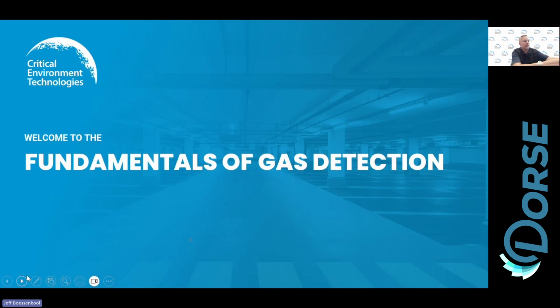We take a larger unit, which is similar to this guy here. We call it our CGAS SD, our sample draw. And we've got a nipple here and polytube going in and sampling that air within that room. The main controller would live outside of the Faraday cage, which is that MRI room, okay? So that we can continue monitoring those oxygen levels and making sure they're at a safe level. If they do get down below, I think it's 19.5 is a low alarm, we can then trip alarms and messages to DDC systems and so on.